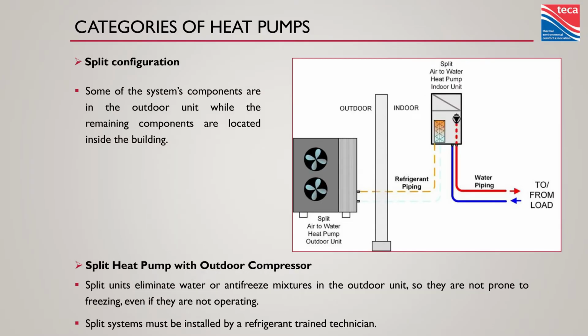Then we have our split heat pumps. So split heat pumps are what we're most familiar with in the air-to-air side of the business. Air source heat pump outside, refrigerant lines bringing that refrigerant into a wall-mounted or floor-mounted indoor unit where it goes refrigerant to water. Sometimes we call that a hydro box depending on the brand. But the wall-hung ones really aren't that unfamiliar to us. It's almost like hanging a boiler on the wall. There's just no venting off of it.